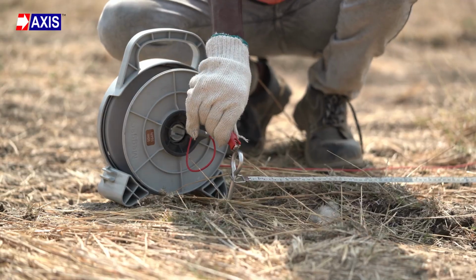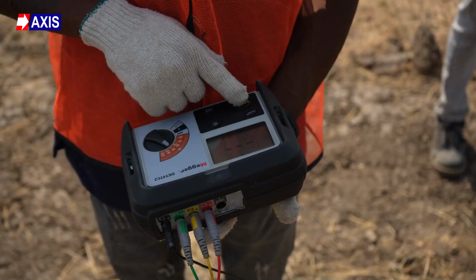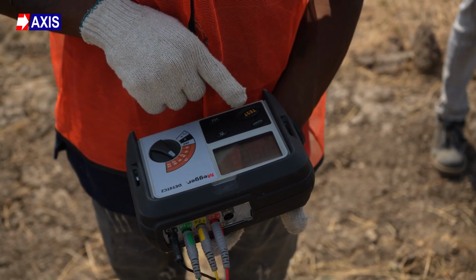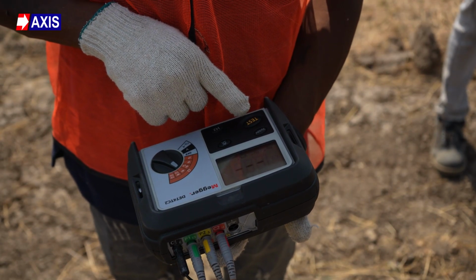When you conduct the soil resistivity test, the data reveals how resistivity varies at different depths. In most sites, the soil is not uniform. It exists in layers, each with a different resistivity value. The mitigation strategy you choose depends on which layer is more conductive. If the second layer soil resistivity is lower than the top layer, add more electrodes. This drives current deeper into the more conductive soil, bringing grid resistance down.